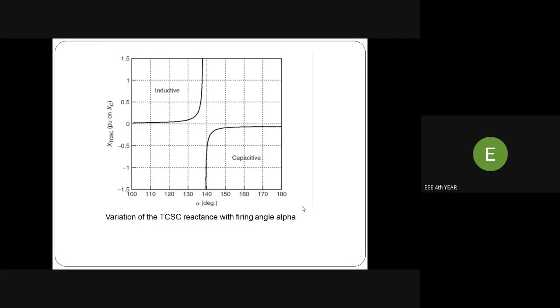Advantages of TCSC: rapid continuous control of transmission line series compensation, and dynamic control of power flow in selected transmission lines within the network to enable optimal power flow conditions and prevent loop flow of power. It is also used for suppression of subsynchronous oscillation, to decrease the DC offset voltage, to enhance the level of protection for the series capacitor, and to support the reduction of short circuit current during events of high circuit current.